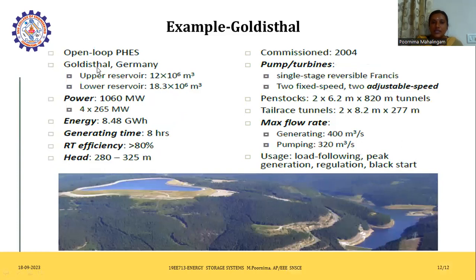The last example is in Germany. Here we can see the picture. The upper reservoir is 12 times 10 to the power 6 cubic meters, and the lower reservoir is 18.3 times 10 to the power 6 cubic meters. The total power produced is 1060 megawatts, and the energy is 8.48 gigawatt-hours. The generating time is 8 hours, and it uses a single stage reversible Francis turbine.